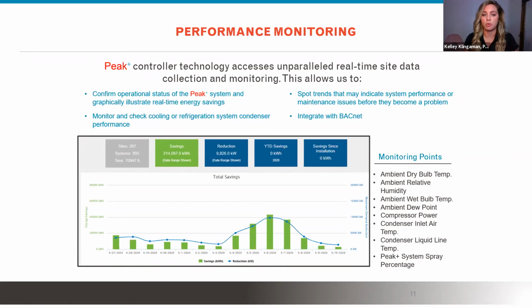As you can see, we're monitoring several points, all of your ambient conditions, your dry bulb, wet bulb, relative humidity, condenser liquid line, and a few other things. So we've got a weather station installed on one of the units. So we're monitoring all these points, and based on what our controller is reading, we know exactly when to turn on our system, when to spray, how long to spray, and what the gap times are in between our sprays, so that we are achieving the greatest effectiveness while also using the least amount of water.